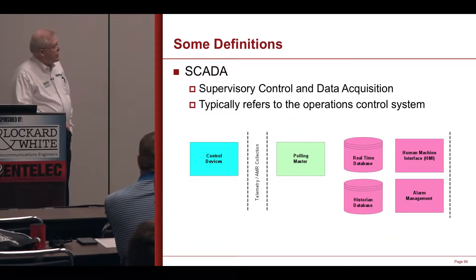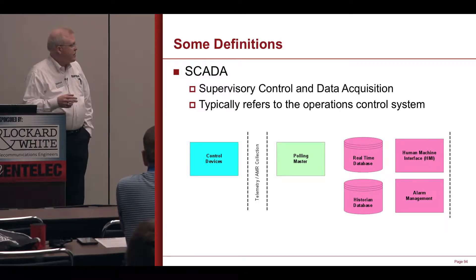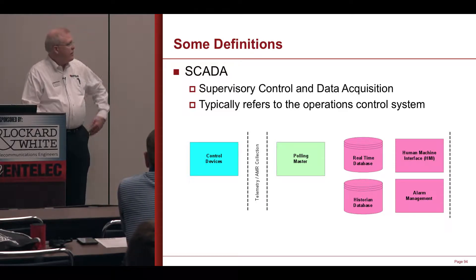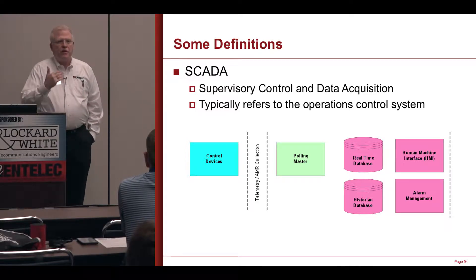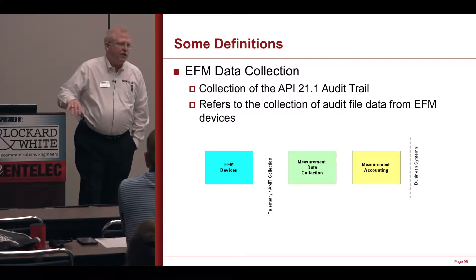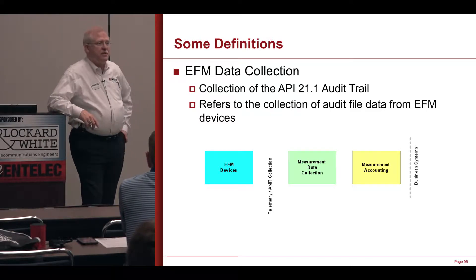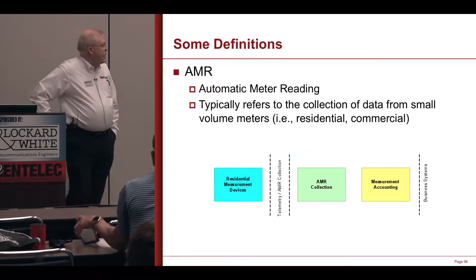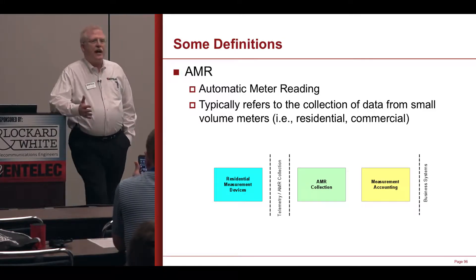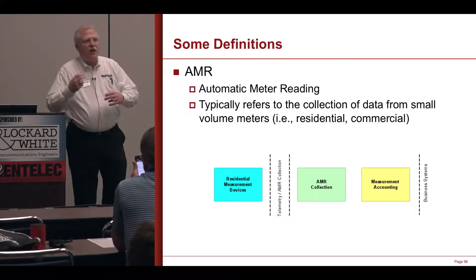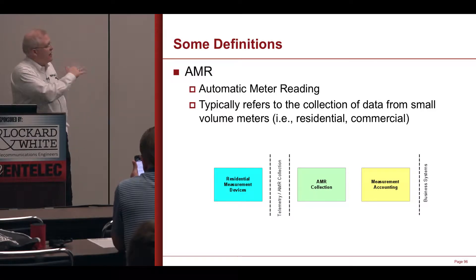What I'm doing is taking that overall data flow and breaking it down into pieces. A simple control system is all you need at a compressor station — you don't need all the EFM and measurement stuff. If you're just collecting measurement data but not doing any control or monitoring, you just need those pieces. If you're doing automatic meter reading — residential gas or electric meters, reading lots of meters maybe once a day or once a month — there's more processing after collection to normalize the data, but those are all the pieces you need.